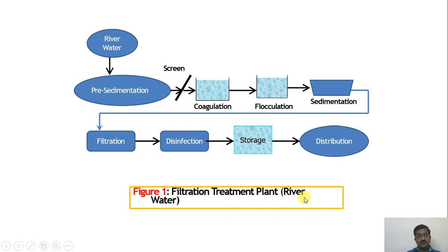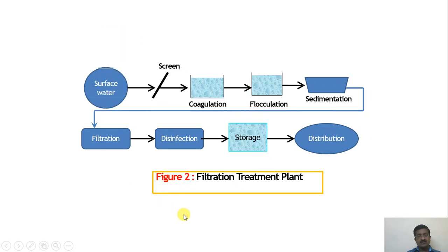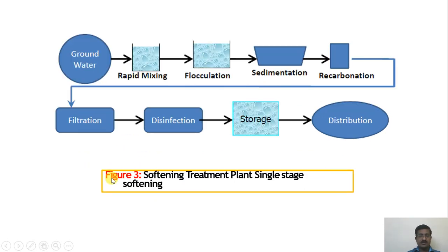Depending on the water source adopted, there may be changes in the flow diagram. For surface water, the sequence is: screening, coagulation, flocculation, sedimentation, filtration, disinfection, storage, and distribution — the same standard process. For a softening treatment plant with a groundwater source, the sequence includes rapid mixing, flocculation, sedimentation, and recarbonation before filtration, to address hardness or high TDS in groundwater.